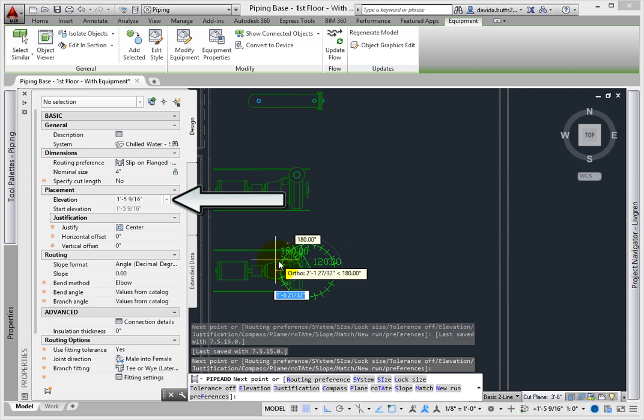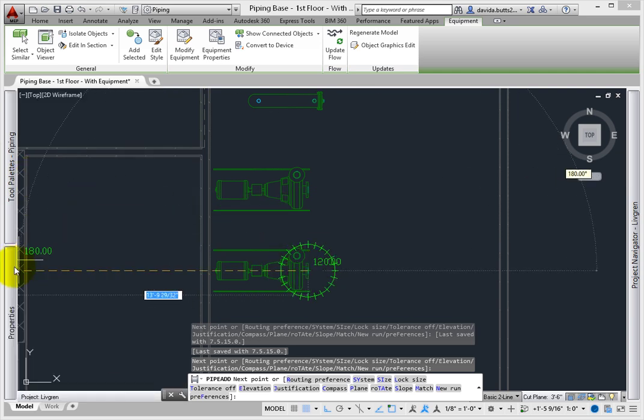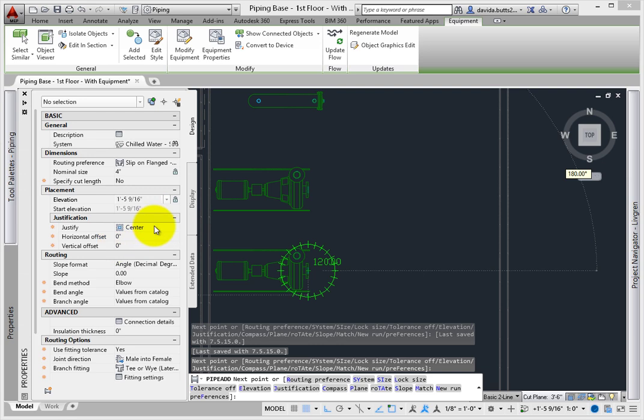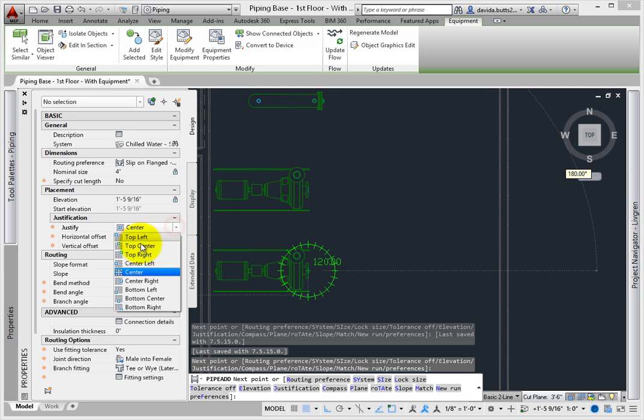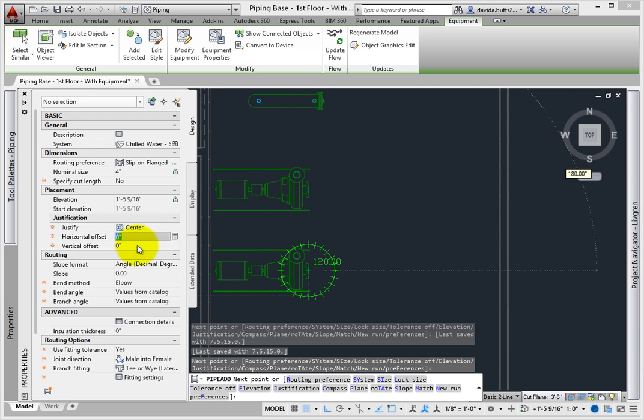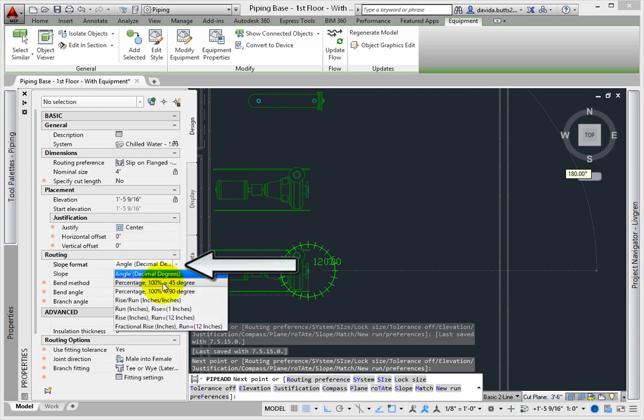Specify elevation has been set by the center on the suction connection of the pump. If you change this elevation, the program will automatically create a riser, unless that option is turned off in the pipe preferences. Leave it as is for now. Justify sets the control line for creating the pipe. If you want to use eccentric reducers automatically, route the pipe by one of the edges, but for most layouts leave this set to center — you can adjust the justification later. The offsets are great for running parallel pipe; we'll leave these alone for now. Slope controls the angle measurement based on predefined pipe references — choose what fits the material and system best; we'll use angle.